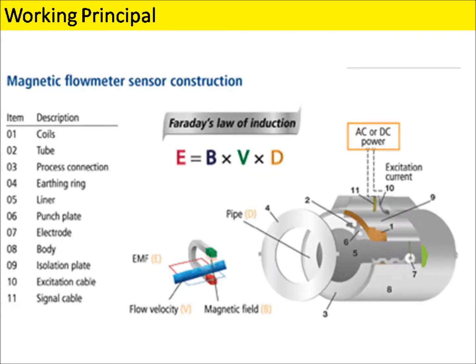High school physics tells us that a conductor passing through a magnetic field will generate a voltage that is proportional to the speed with which the conductor is moving. You might recognize it as Faraday's law of magnetic induction. In the case of a magmeter, the liquid itself is the conductor, and the magnetic field is created by coils placed around the pipe. Two electrodes placed on opposite sides of the pipe, perpendicular to the liquid flow, and the magnetic poles measure the induced voltage. The voltage generated is proportional to the velocity, which is then converted to a flow rate.